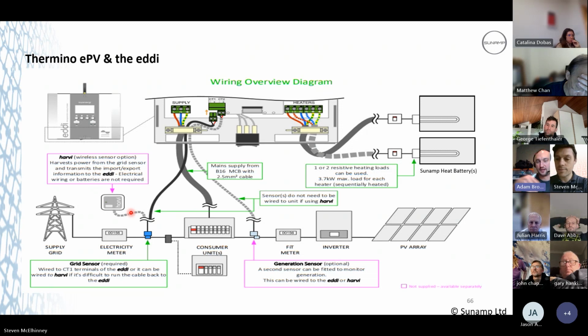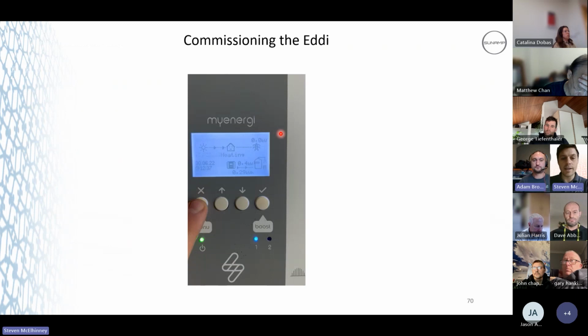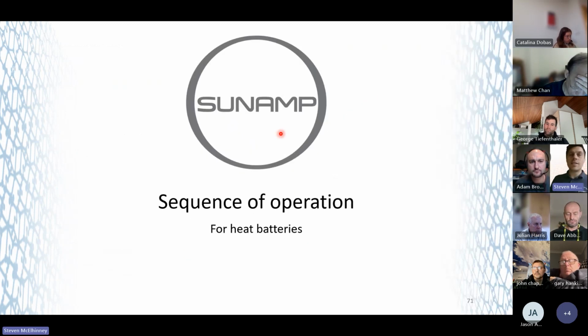You know, the Eddi will allow it to go, but obviously if the heat battery doesn't want the energy, or it's full or whatever capacity, it'll stop. It'll stop itself within the electronics of the SunAmp heat battery itself. So the heat battery will recognise it's up to temperature and basically break the circuit of the electricity flow. That makes a little bit more sense. Yeah. That's the only thing to remember: just get the time boost set, because if you just set it constantly on, or the customer just relies on pressing the advance button, it will either never reach temperature or it will just constantly charge.